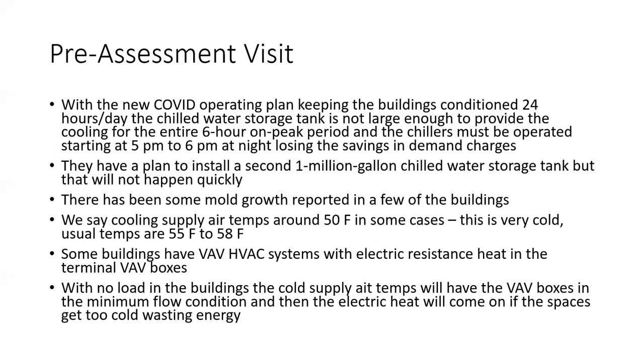Usually design will be 55 to 58 degrees. There is a concept that circulated around a number of years ago, 10, 15 years ago, called cold air distribution, where buildings were designed with these very low supply air temperatures for air conditioning in order to downsize ducts and fans. You know, if the air is colder, you don't need as much of it for a given load.